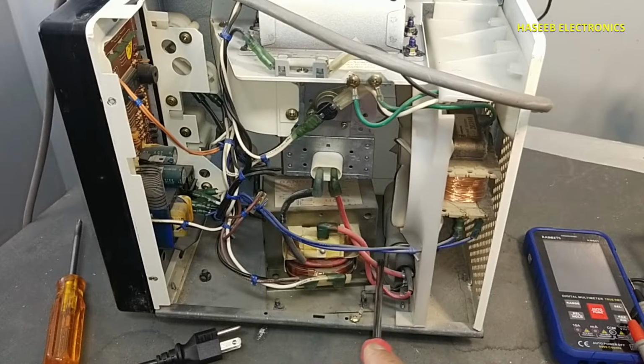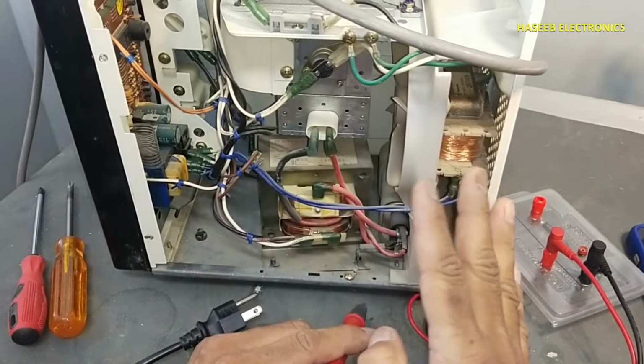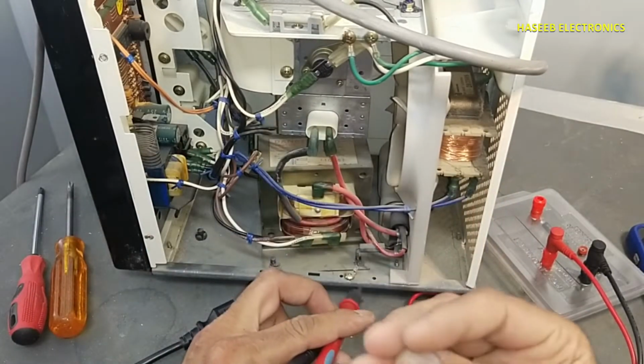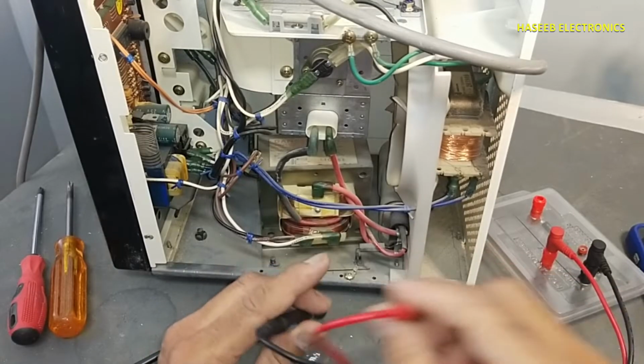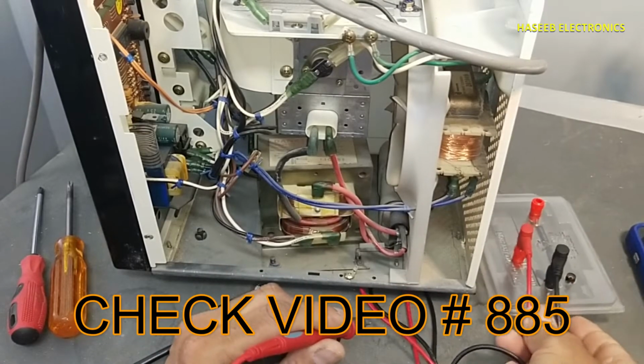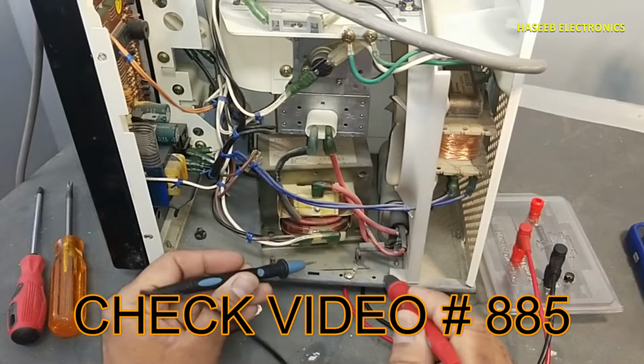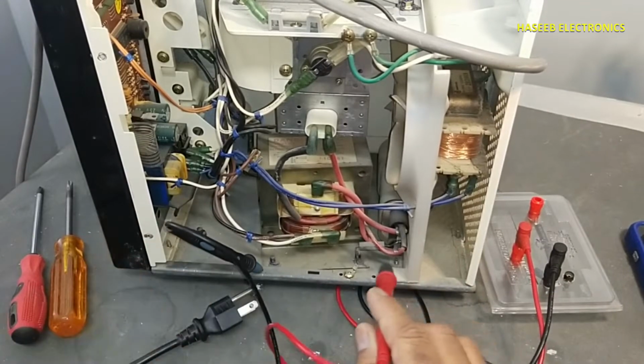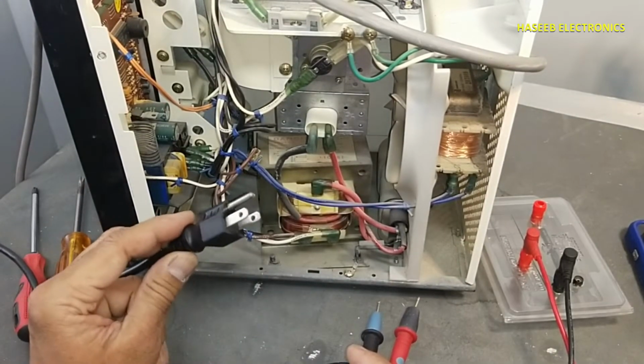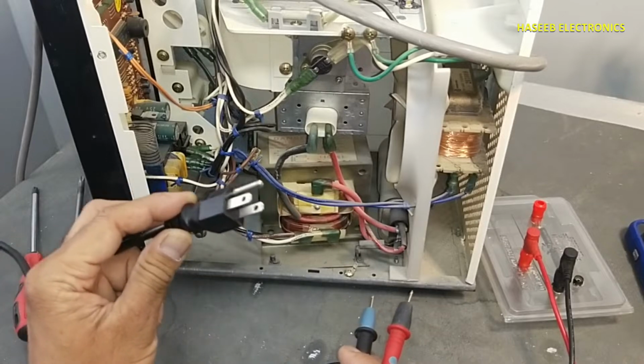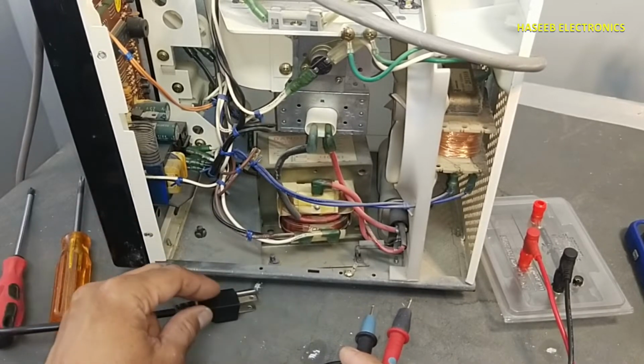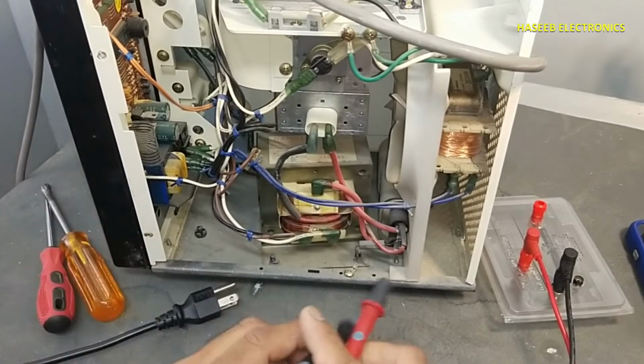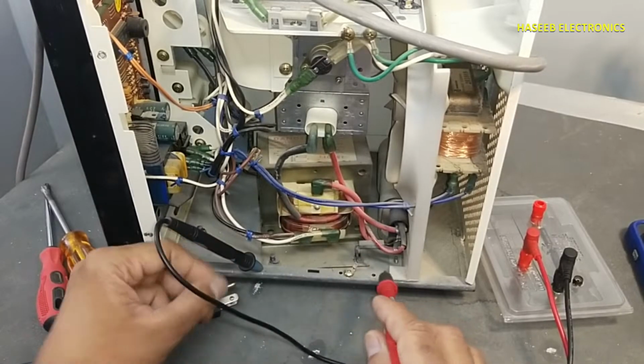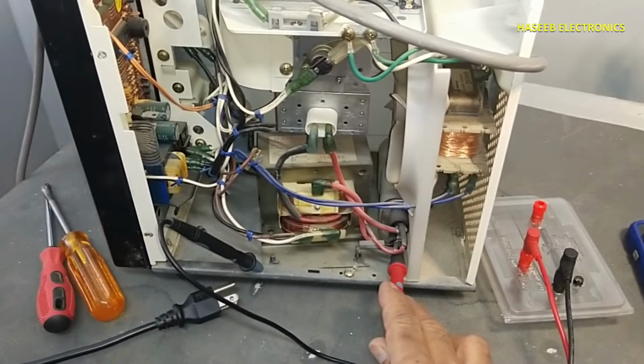We need to discharge this high voltage capacitor before touching this device, this circuit, before starting troubleshooting. If you have a high voltage discharging kit, you can use this discharging kit. During this troubleshooting procedure, whenever we apply power, after removing power, we will discharge it, and it must be ensured.